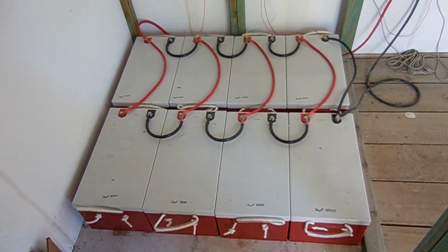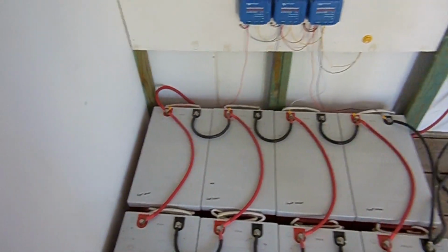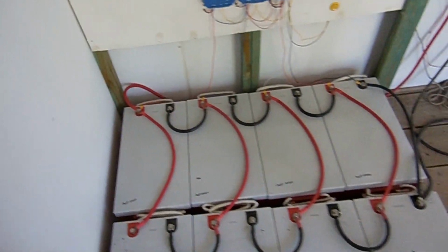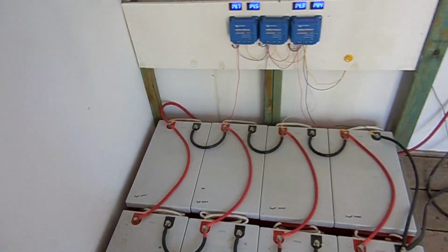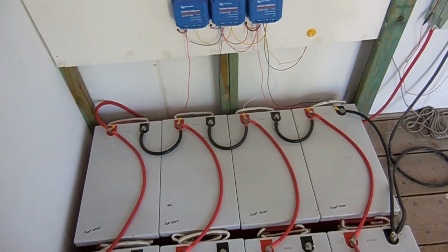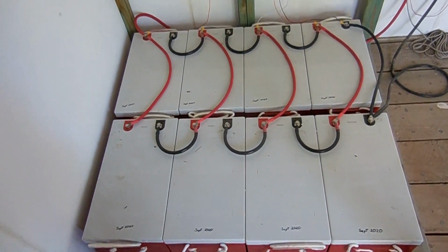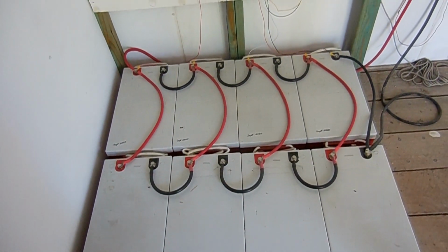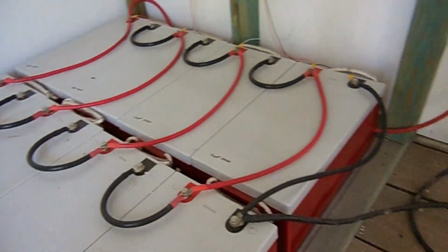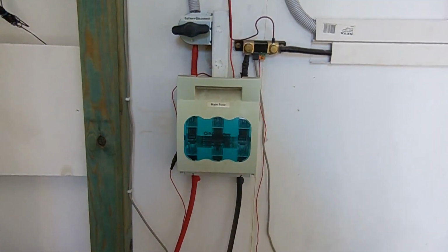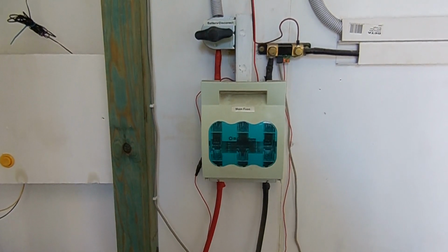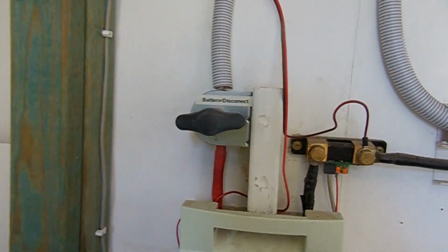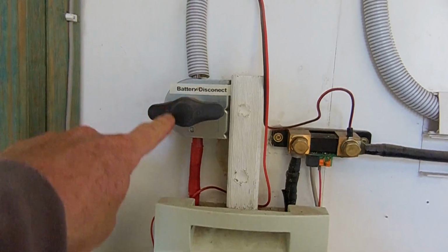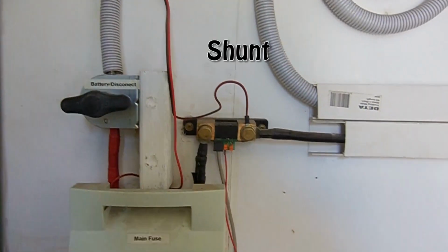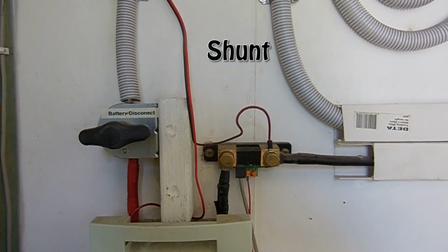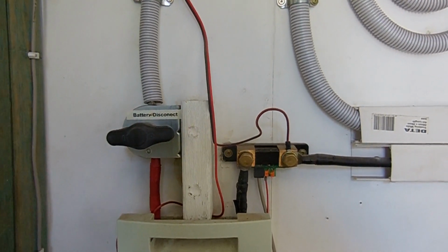Here we have our 48 volt battery bank. These are 12 volt AGM batteries. So they're wired in sets of 4 in series to make 48 volts, and we have 2 banks of 48 volts, and then that's wired in parallel to double the capacity. From these batteries they go across into a main breaker, which is a main fuse breaker. We have a main battery disconnect switch, and the negative side goes into a bus bar which measures our input and output power coming in and out.